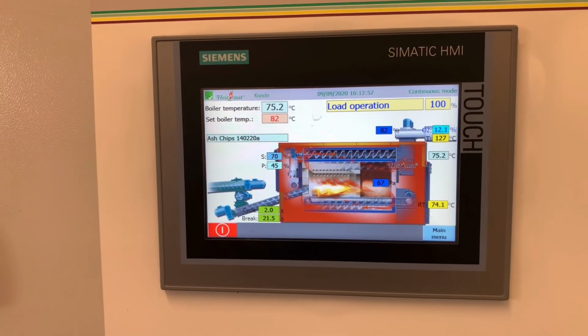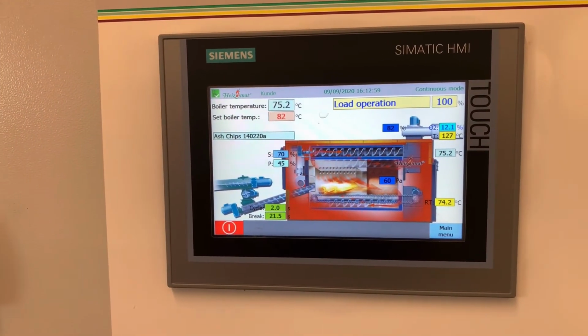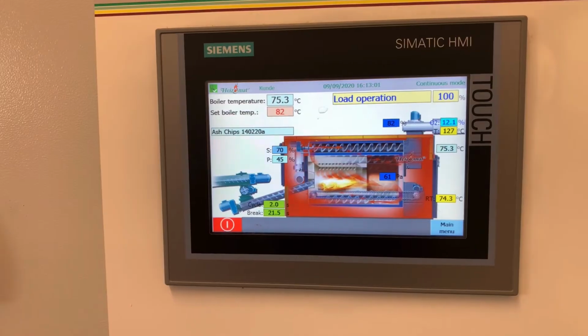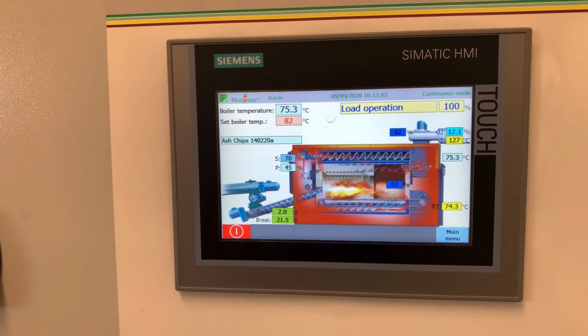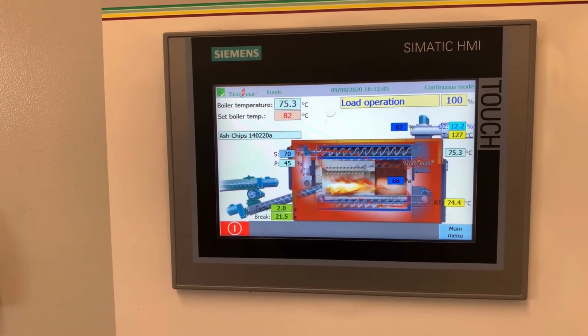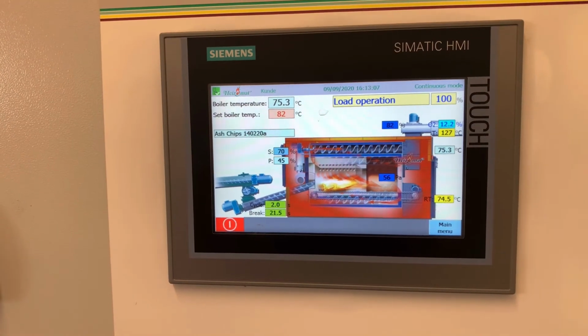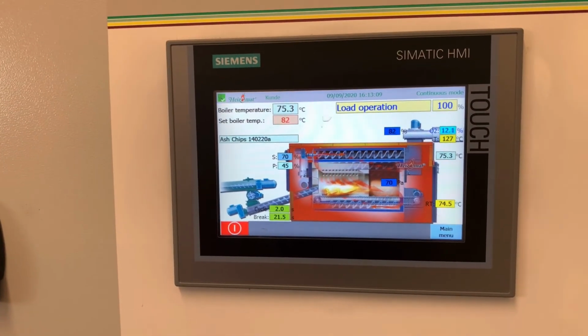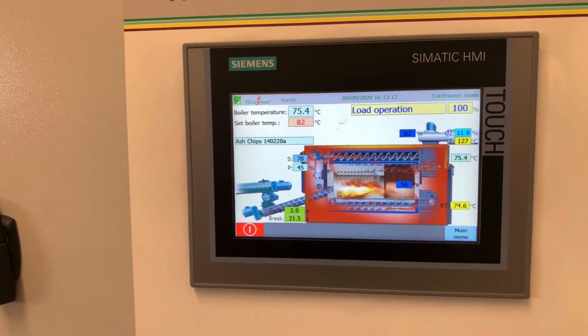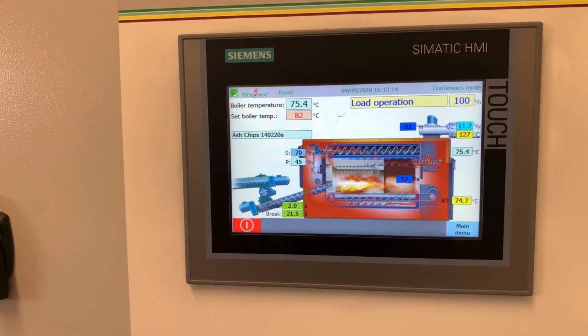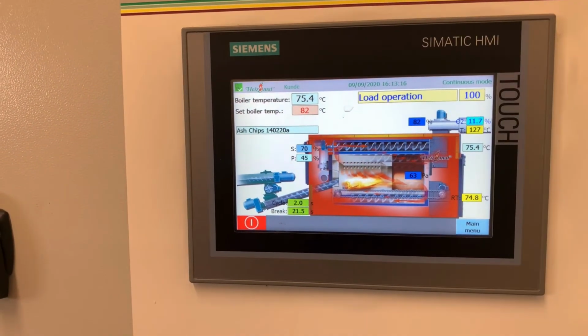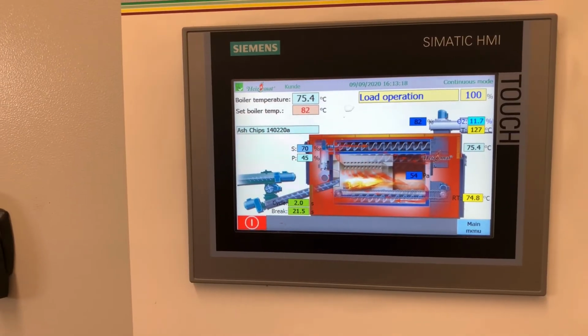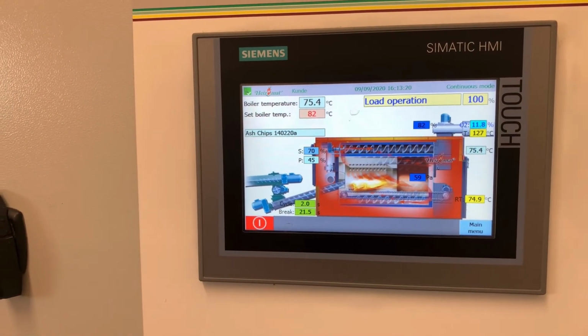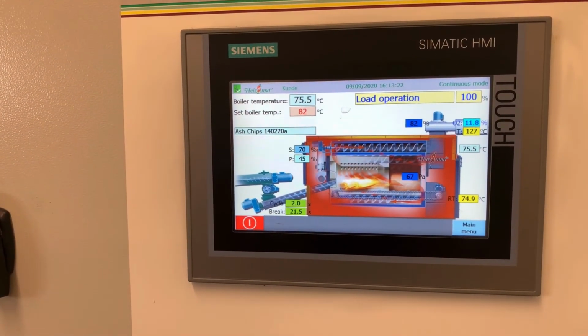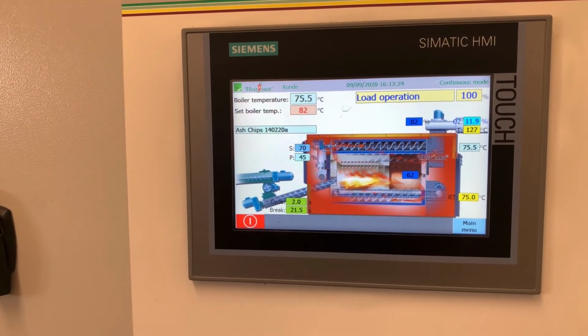So the other thing about the control panel is this is where the alarms would show up. So if anything happens with the boiler, say we open one of the flaps that has a safety switch on it, or if something got jammed in the boiler or ran out of fuel, we would get an alarm on the boiler. And so this is where you would come to check what the alarm is and reset it. It's also internet connected, so if you did get an alarm, it will send an email to you on your phone so that you're very aware that the boiler does need attention.